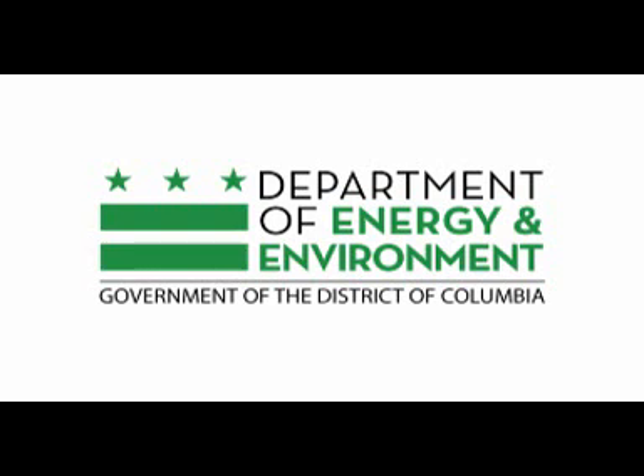I'd just add here, I would agree that poor performing buildings often may not have a sense of what equipment needs to be upgraded when or how they're going to do that. I think it's bigger than equipment too, though. It's also about operating schedules and procedures and processes for going back and rechecking that on a regular basis, to make sure that someone didn't just say, oh, this system isn't working right, we'll just flip the hold switch, and then someone forgets about it. At the more extreme end of that, from a rigor standpoint, you have things like regular retro-commissioning check-ins, which may be something that could be considered or recommended.